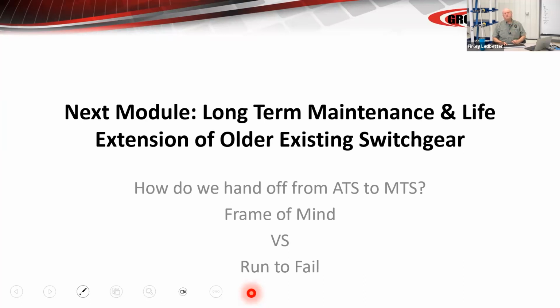If you've got equipment that was put in the last 10 years, you've got a different class of equipment. The insulating material is different. The electronics and the wiring is different. Everything is different. Now, there are some advantages to the older equipment. There are some disadvantages to the newer equipment. The older equipment dealt with weight of copper and mass, where the new equipment typically works with speed and contact pressure to get the same ampacity through the breaker.